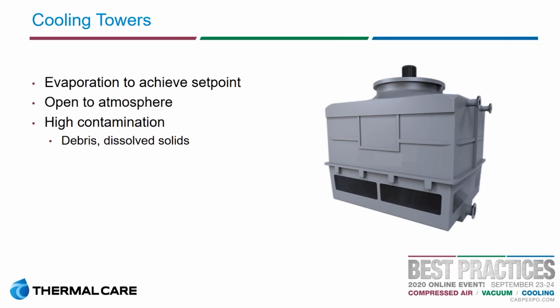So if that water is now pumped out to the machines that you're using, you risk that potential contamination. You also have actual evaporation occurring. When you evaporate water, only the water leaves, so all the dissolved solids, everything else stays behind. So you can get very high concentrations of dissolved solids in there. One of the things that needs to be done is the water has to be chemically treated, but you will also need to consider pumping off some of that high concentration water to then be refilled with a lower concentration, to maintain that level of dissolved solids so it doesn't hurt the operation of the system.